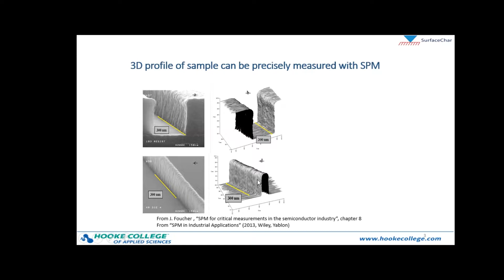So briefly, I just want to review the principles of operation of AFM so that we're all on the same wavelength. We have a very small cantilever with a sharp tip hanging off the end. This cantilever has the dimensions approximately of a human hair, and this tip cantilever assembly is typically made of silicon or silicon nitride. So this is an SEM image of the cantilever, and it's placed right here. And then we have a laser that's reflected off the back end of the cantilever and then directed towards a position-sensitive detector, which can monitor the up, down, or side-to-side motion of the cantilever as it interacts with the sample.